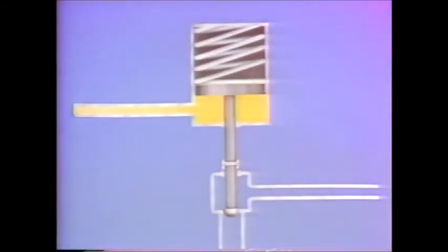Well, now that we've seen how the control and intercept valves work, let's take a look at stop valve and reheat stop valve systems. We mentioned earlier that these valves are either positioned fully open or fully closed. This makes control of these valves much simpler. Their actuators are like the control valve actuator we've already seen.